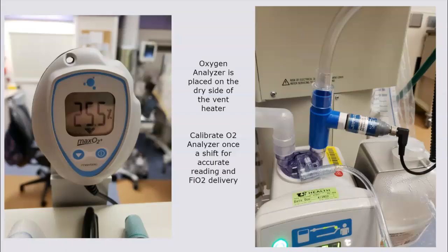To adjust it, to make sure we're giving accurate and appropriate oxygen, we use an oxygen analyzer. The only time we'll take this out is if we put nitric in and there's an analyzer in the inhaled nitric setup. But for the oxygen analyzer, you just use an open T-piece on the dry side of the heater.